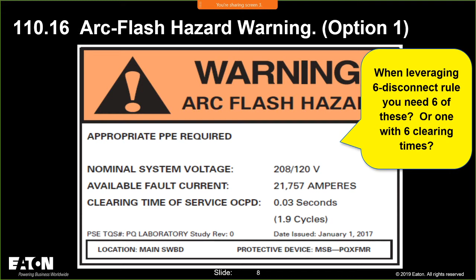But in reality, I don't believe this is really where you want to go because it doesn't provide the electrical worker the information they need to work on that service entrance equipment, because they need the clearing time of the upstream overcurrent device, not the devices that are in that panel board. You know, this is where you probably should be going right now as it stands with regard to 110.16b, because you're following 70E, which is leveraging IEEE 1584 for arc flash calculations and so on.